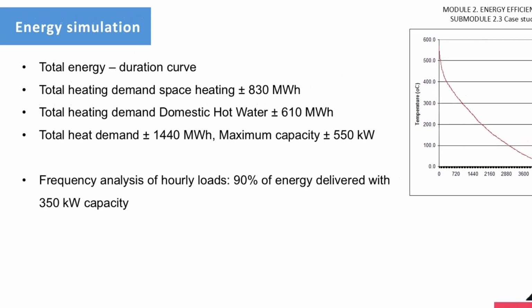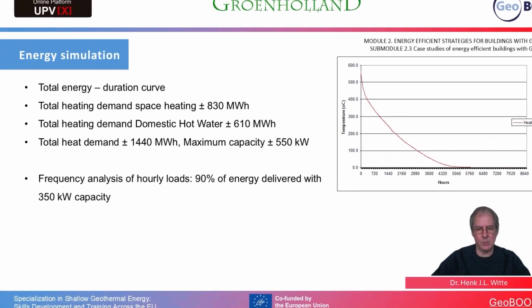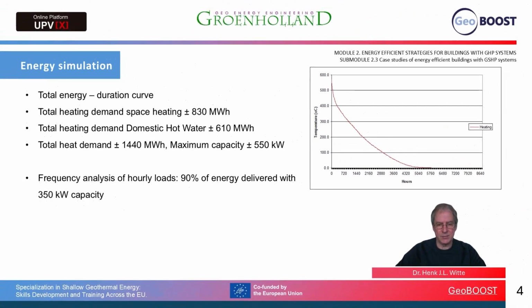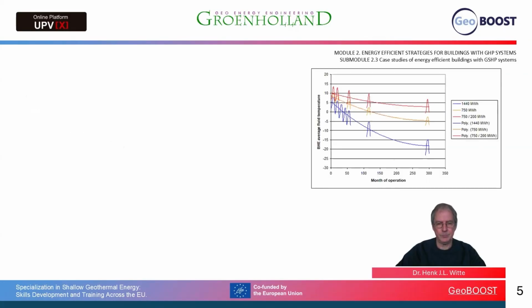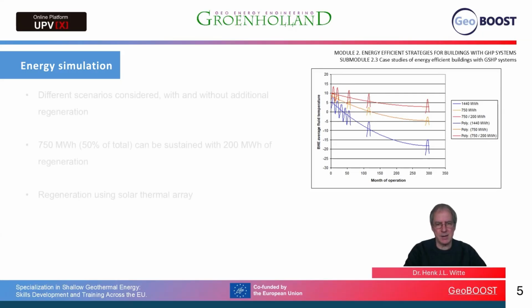At the same time, we can see, if we analyze the frequency analysis of the hourly loads, that about 90% of the energy can be delivered with 350 kilowatt capacity, which is, of course, significantly less than the 550 kilowatt. Now, using this information, we started to retro-engineer the borehole field. And the question was, how much energy and peak capacity can the borehole field sustain? We looked at all kinds of different scenarios with and without additional regeneration.